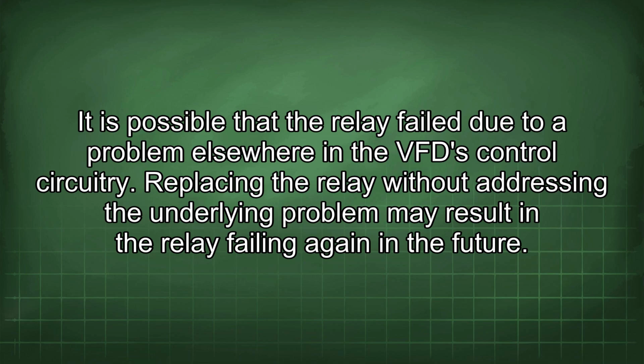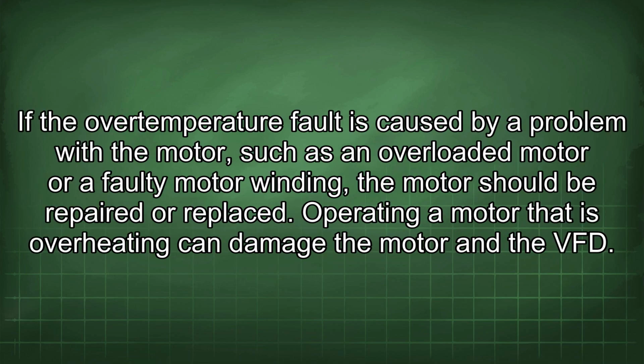Replacing the relay without addressing the underlying problem may result in the relay failing again in the future. If the overtemperature fault is caused by a problem with the motor, such as an overloaded motor or a faulty motor winding, the motor should be repaired or replaced. Operating a motor that is overheating can damage the motor and the VFD.